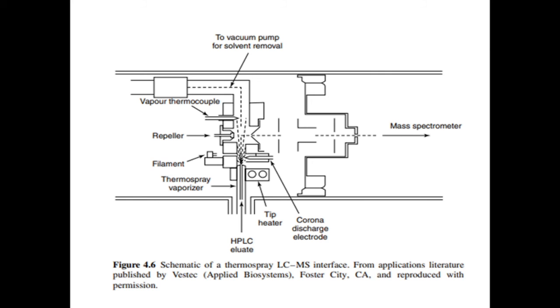It should also be noted that the effect of the repeller is both compound dependent and mode dependent, that is thermospray, filament or discharge dependent. It is necessary prior to developing any analysis, therefore, to determine the optimum experimental conditions for the analyte of interest.